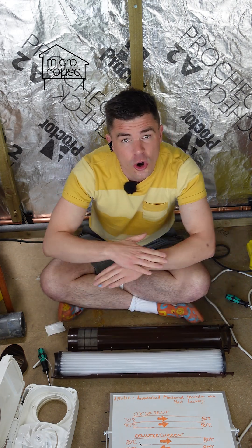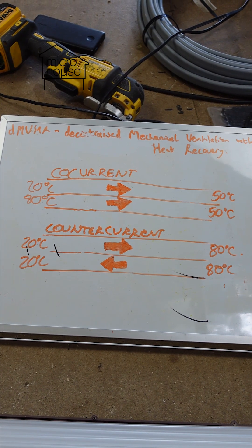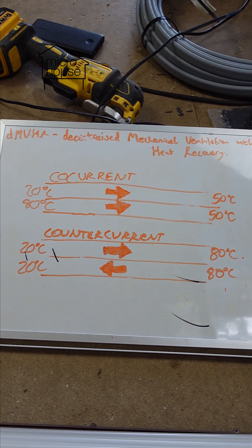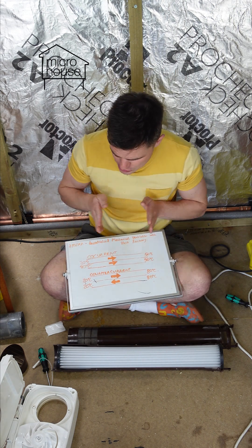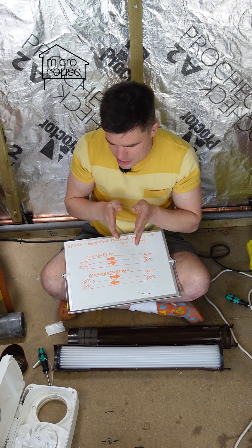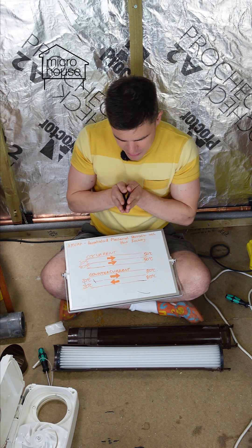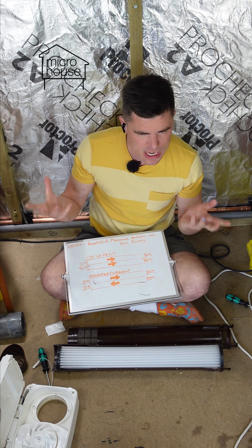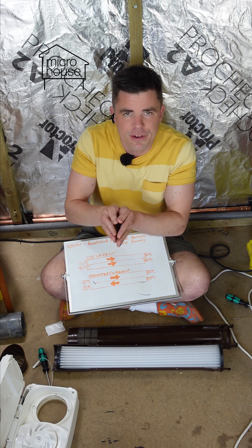separated but contacted. And this uses a principle called counter current heat exchange to try and preserve as much of the heat in the inside air as possible. Firstly, if we talk about co-current heat exchange, if you can imagine two fluids passing beside each other in contact with each other, but not mixing, if one of them is 20 degrees, one of them is 80 degrees, given enough contact and enough time or distance, they'll eventually become the same temperature as each other. And that's quite easy to understand — eventually they'll become 50 degrees or so.